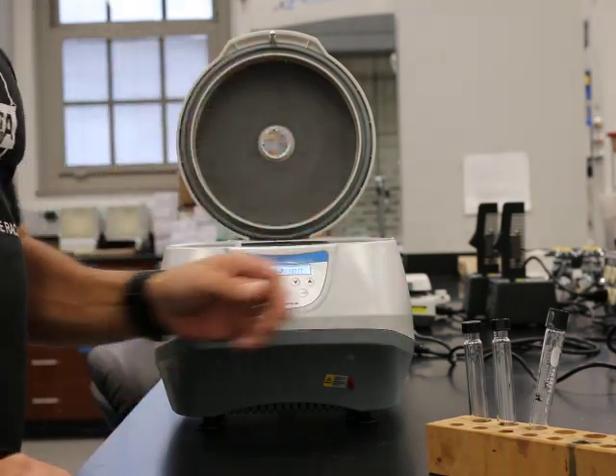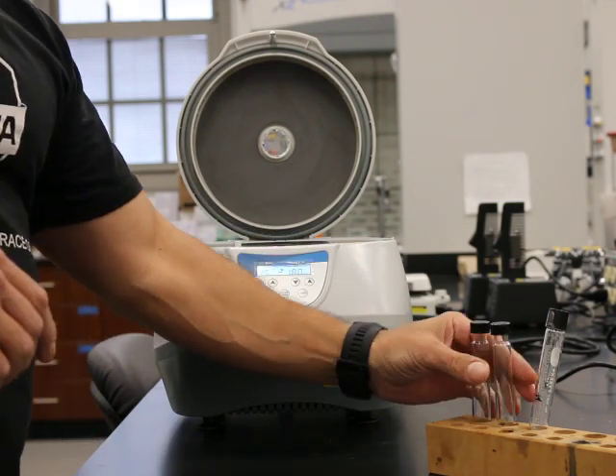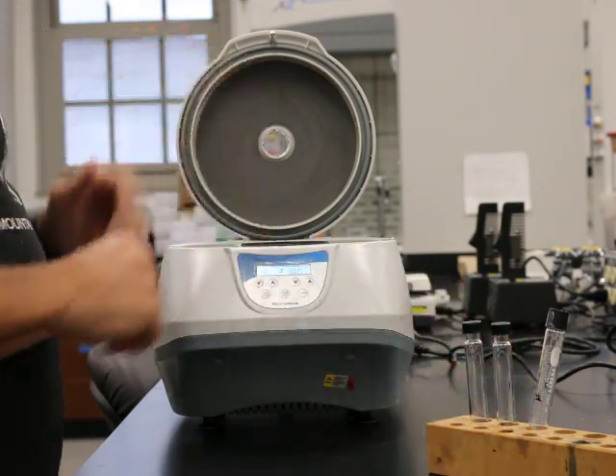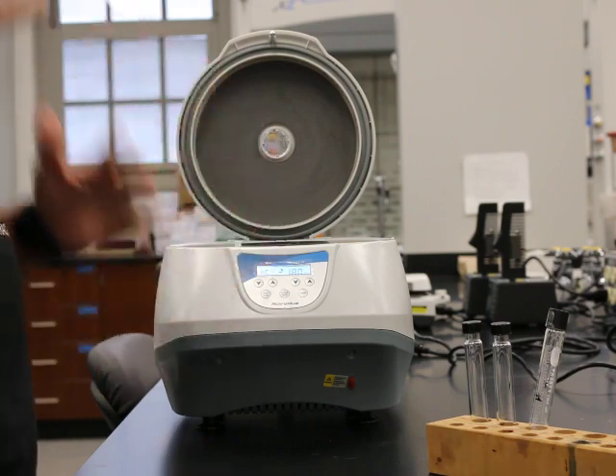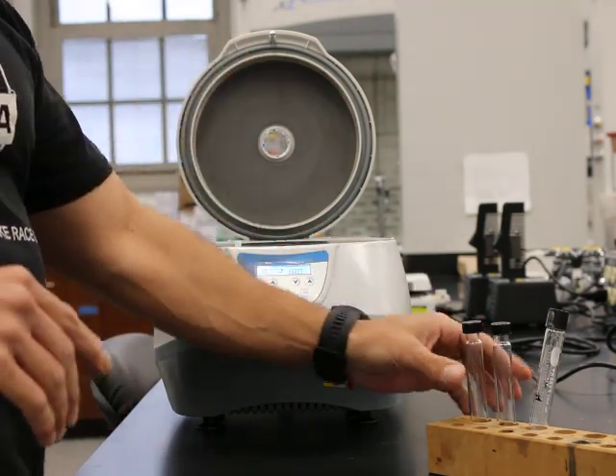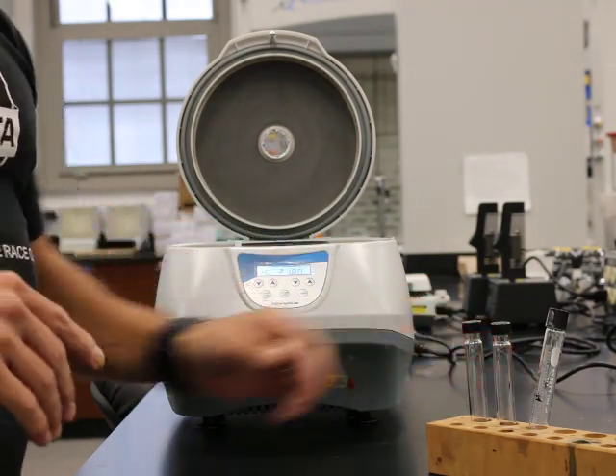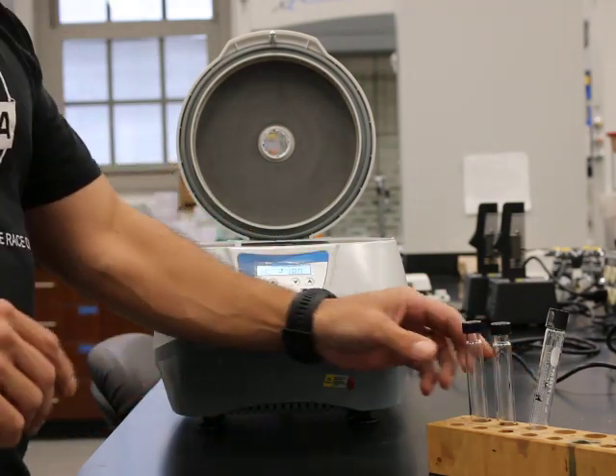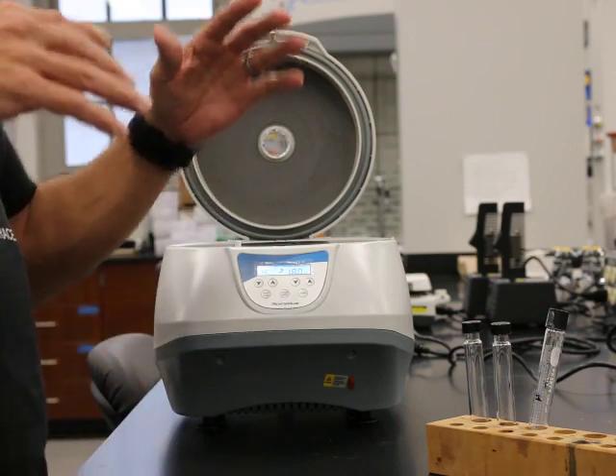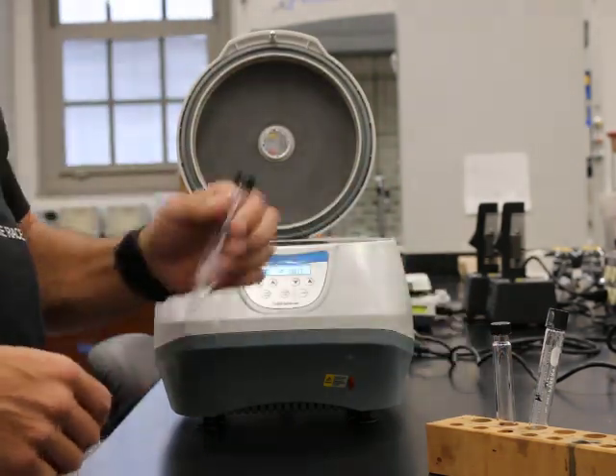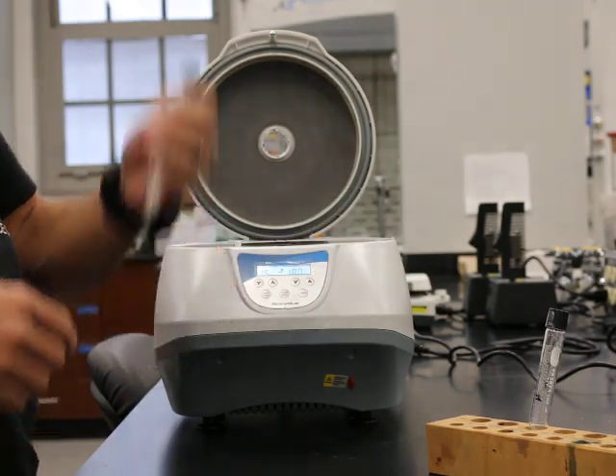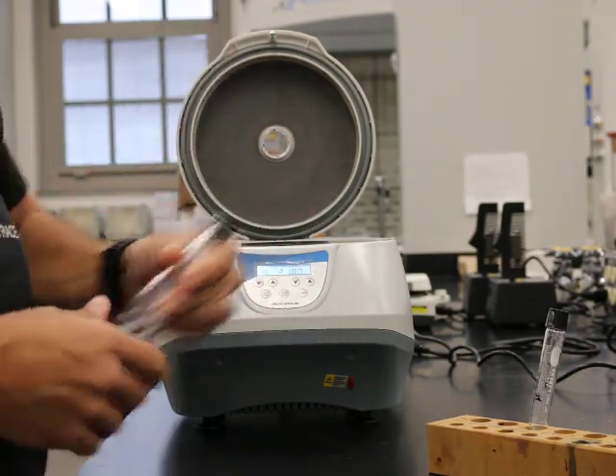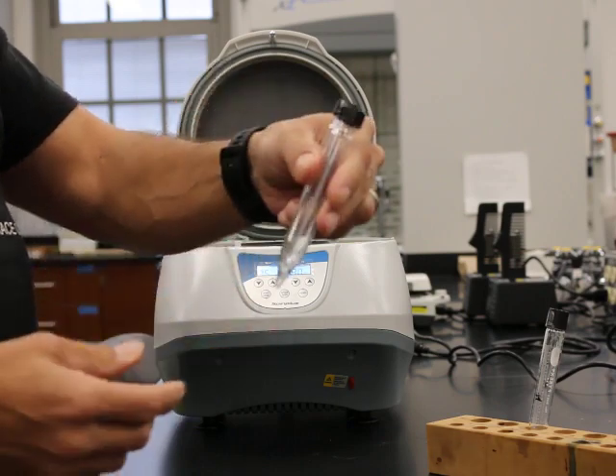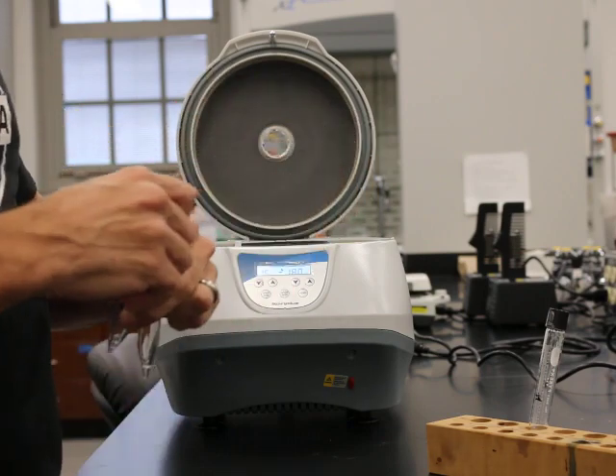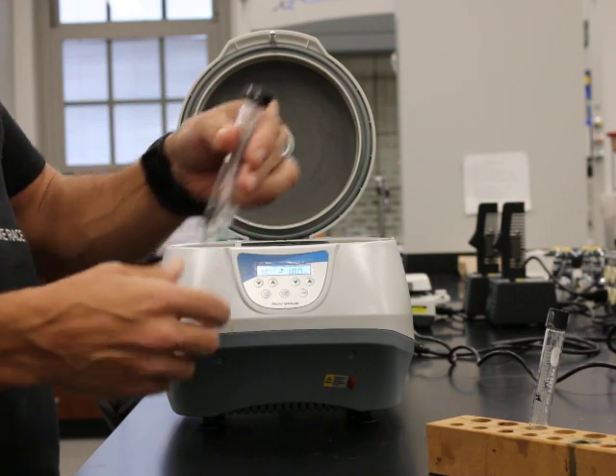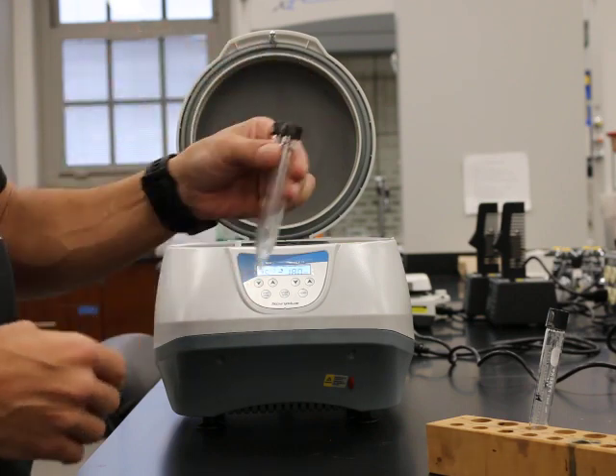The main thing to know about the high-speed centrifuge is anytime you use it, the load has to be balanced. If it's not balanced, it's going to bounce around and you can break your centrifuge tubes and damage the device. So to balance it, what you need to do is either be working with someone who has a centrifuge tube which has the same amount of liquid in it as you, or you may have two centrifuge tubes. You need to make sure that both centrifuge tubes have the same amount of liquid in them. There can't be a major discrepancy between the two.